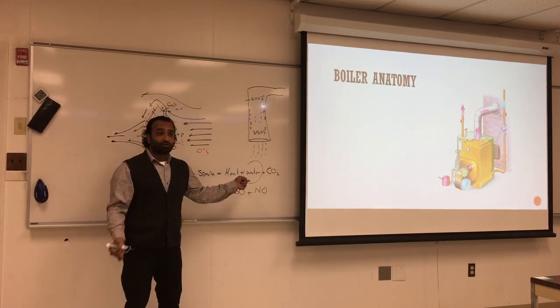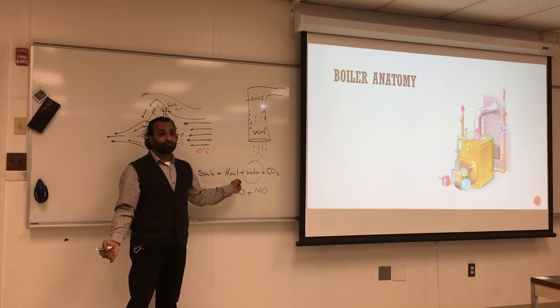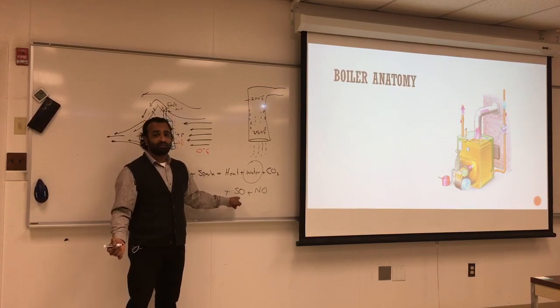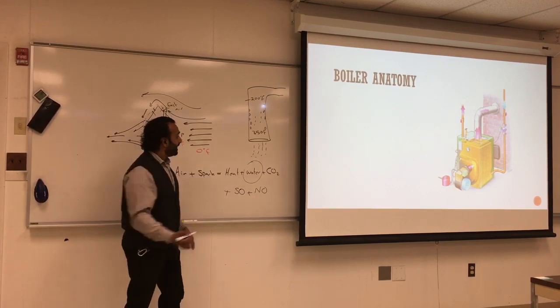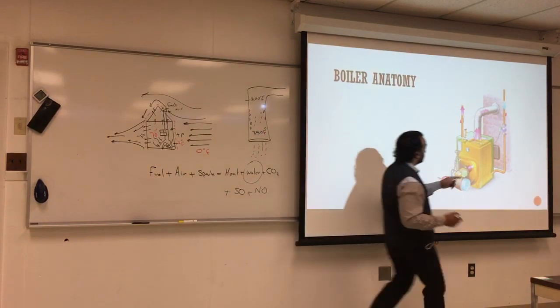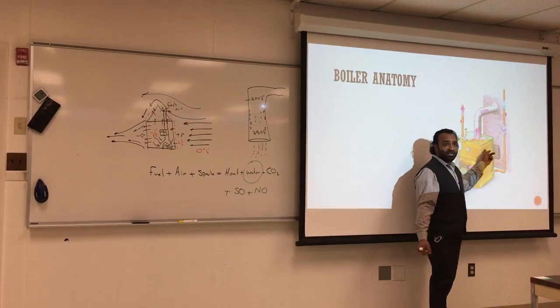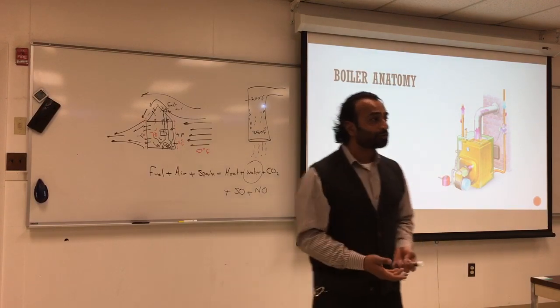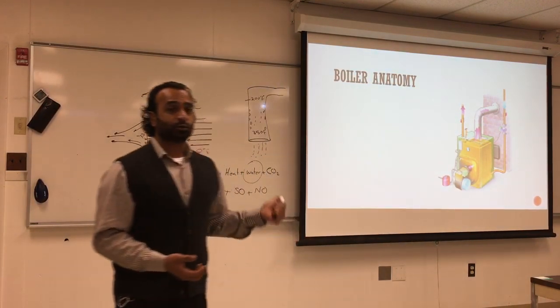So you're lucky if it's completely water, because water is corrosive, but it's not as corrosive as sulfur oxide. Sulfur oxide will eat your pipe, and it will drip back into the heat exchanger, and it will eat it out, and eventually it will have holes, and that will ruin your boiler.